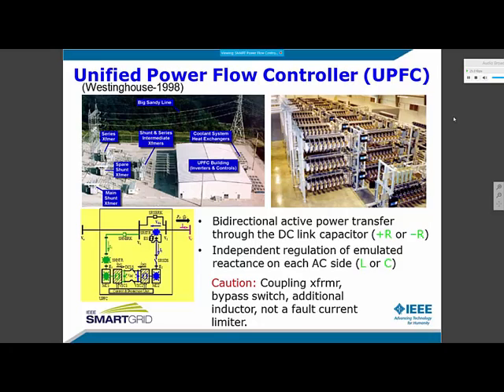The side effect of impedance regulation with an inverter is that a series-connected compensating voltage needs to exchange bidirectional real power with the line. One way to accommodate this requirement is through a shunt-connected solution, as shown here in this picture. The bidirectional active power goes back and forth through the DC link capacitor. In addition, both AC sides can emulate reactance. Note that this UPFC uses over 800 switches and thousands of components that become obsolete soon after this kind of hardware is built. Besides, this unit is not practical for relocation. Even though it is a power electronics-based solution, as you can see in the switch here, there is a transformer that has a rating way over the rating of the power electronics. And later I will show you a solution that uses less transformer than this and no inverter whatsoever to do the same power flow control capability.